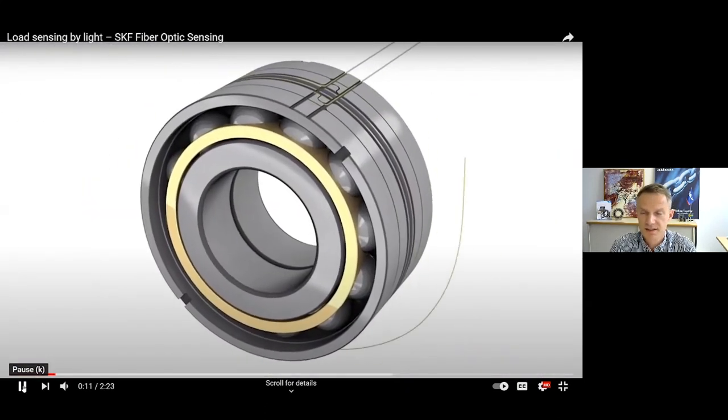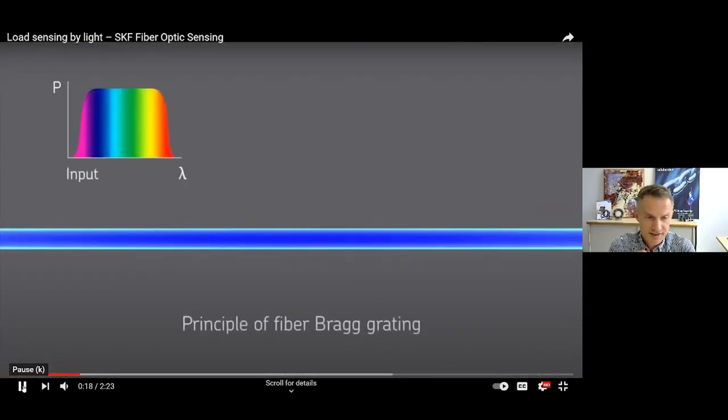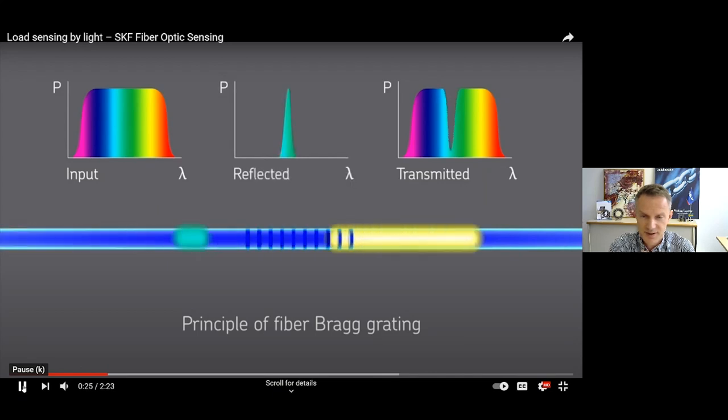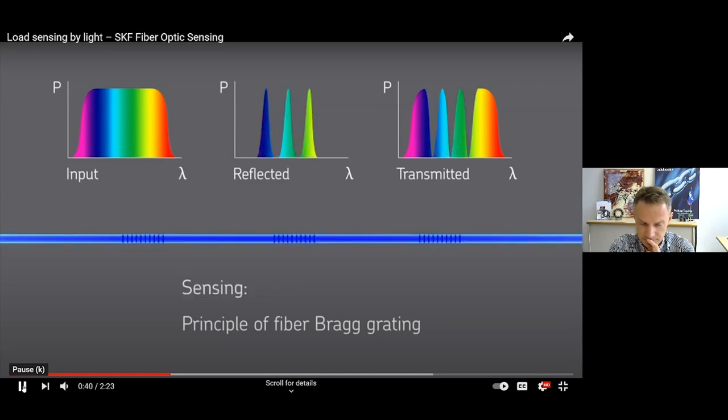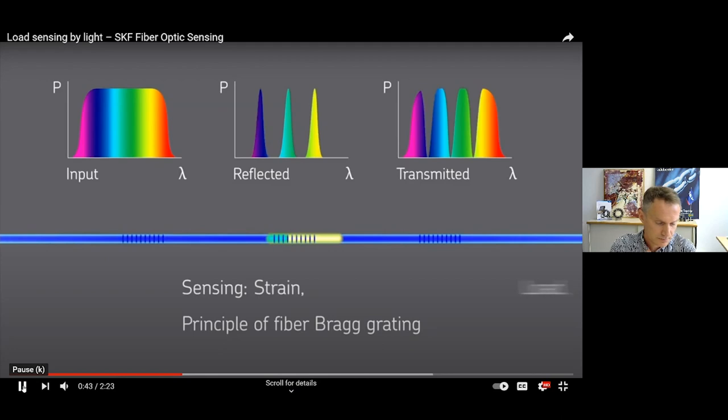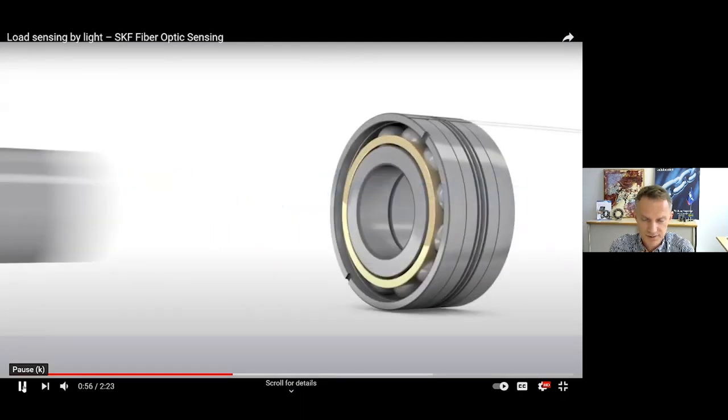This is the fibers that are arranged in a certain way around the bearing. Light is going through the fiber. There is some grating called Bragg grating done on these fibers, which is kind of making some small mirrors into the fiber. Some light is reflected. At this you can measure the elongation of the fiber similar to a strain gauge.